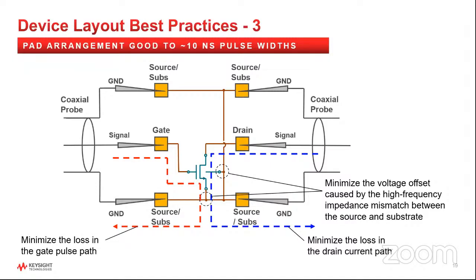But as I'll explain, the downside of this is that you are using RF probes, which can again be very expensive. And it does limit you to some extent, because you have to use a very specified fixed pad configuration if you want to go like this. But in general, I'd say for most people, the one I showed previously probably is okay. Again, it depends on what you're trying to do and what kind of pulse widths you're trying to create for your measurements.